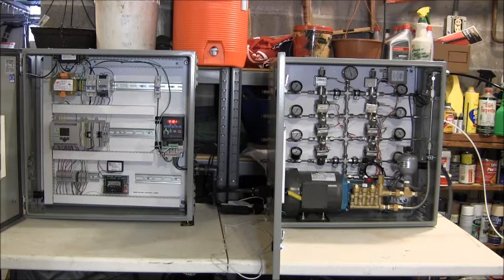And this pump has the capability of 0.3 gallons per minute, GPM. There's the pump itself. So that's a capacity. It can run at 1,000 psi at 0.3 GPM, but we're running at a much lower pressure. You can regulate the pressure through this regulator right here. That can set and adjust the pressure output.